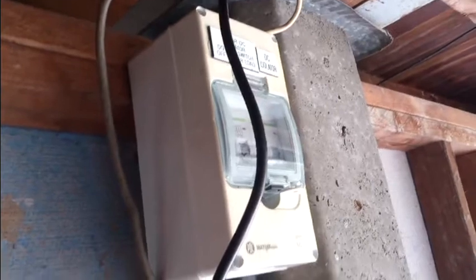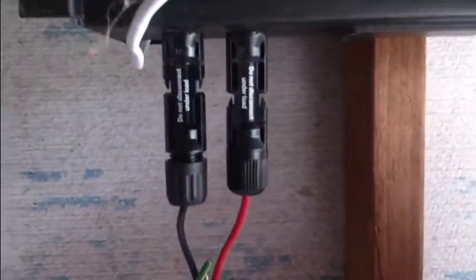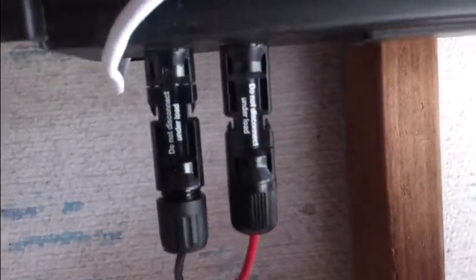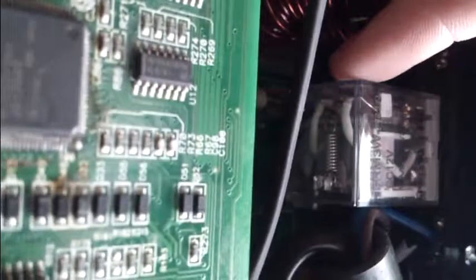The way this works, you've got your solar panels which run, I've got running along that lead there, goes into the DC isolator which isolates both positive and negative on separate switches, all at the same time, they're ganged, runs down into these connects here, which then go into the inverter. Now, the only other change I made was this connector here. I couldn't get, it didn't come with it. This is the AC connector. So I've put a 240 volt plug straight on to the terminals that are just behind here, which I've since moved on to this relay switch to turn it on and off. That's a double pole, double throw. Basically, it can be either normally open or normally closed, depending on how you set it up.